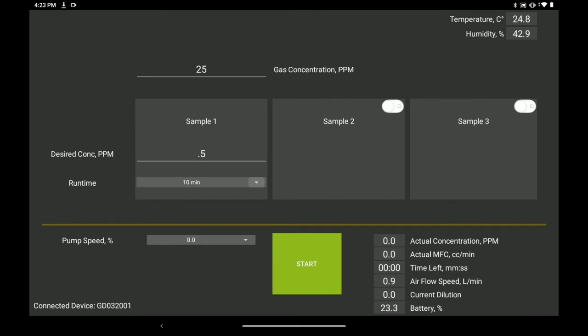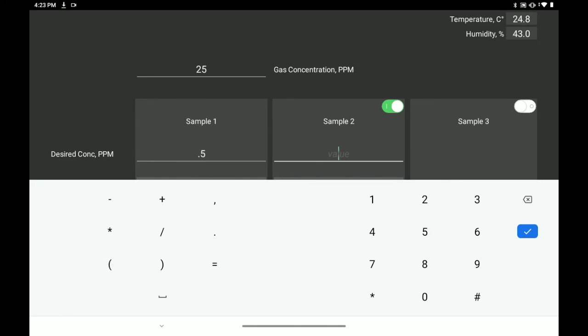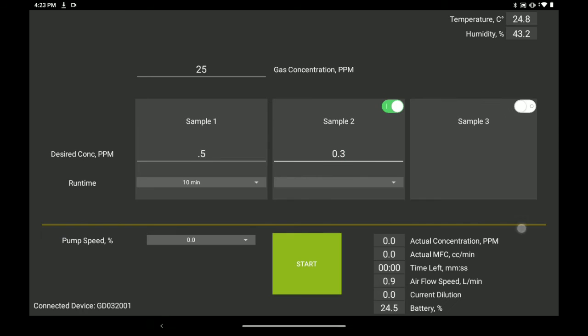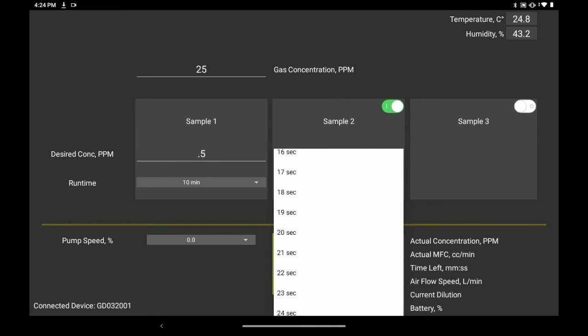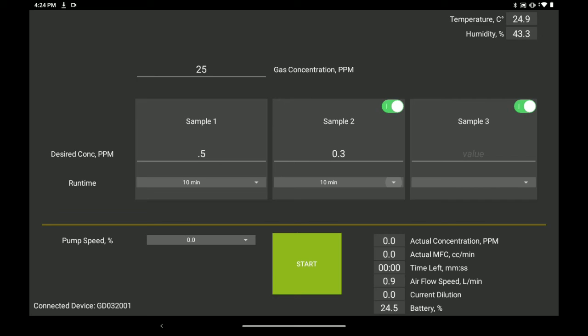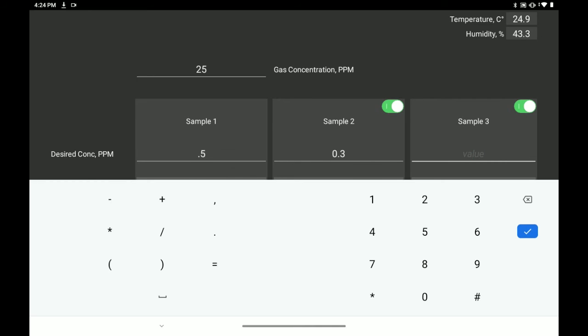One of the cool features of the GD600 is that you can perform multiple point calibrations automatically. To automate this, all you want to do is check point sample 2. And once you do that, you can enter in the second value. Always when you're calibrating a Centroid gas analyzer, we recommend that you start at a higher dilution and work your way to lower dilution. So the next one I'm going to put at 0.3 ppm. And again, I'm going to run that for 10 minutes. And I can do the same thing for the third point to make it a true 3-point calibration.